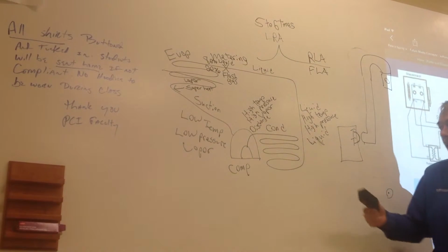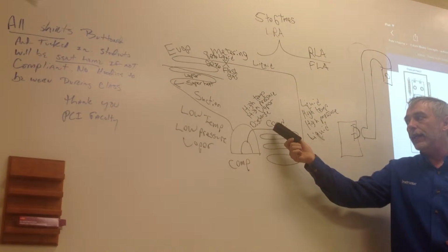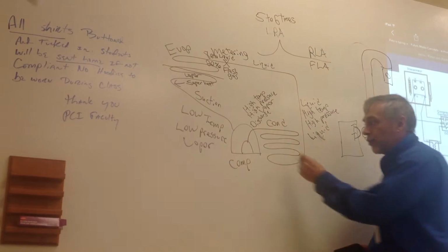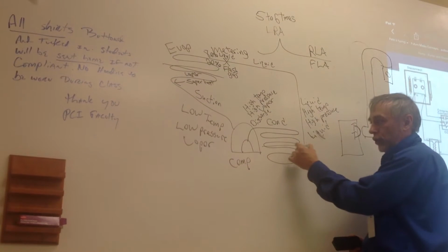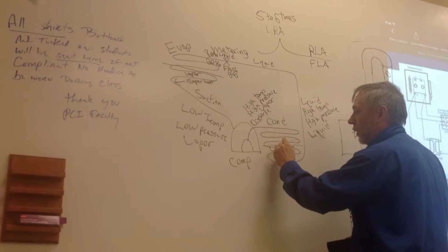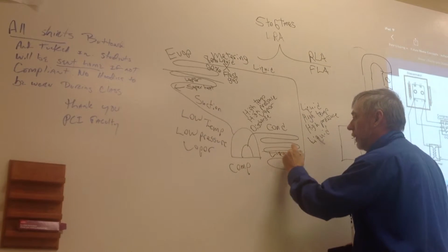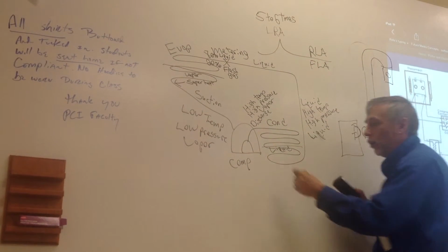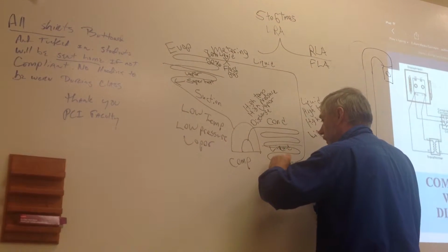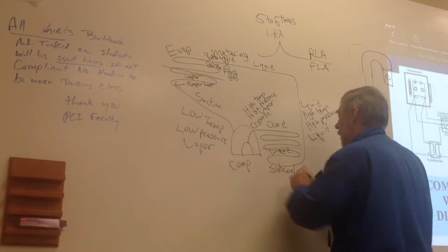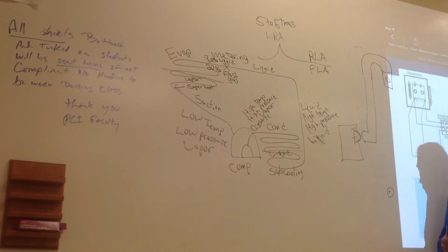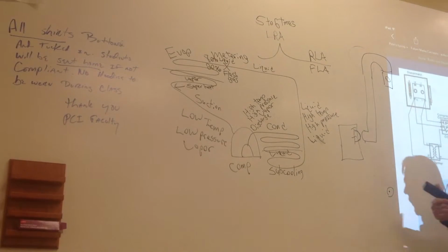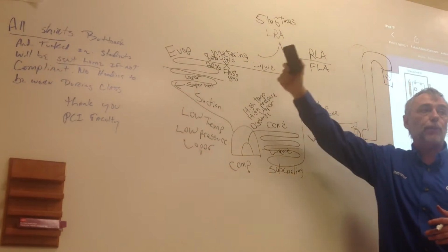And then on the other side over here, where we have taken that high temperature, high pressure vapor and condensed it, approximately 40 to 60% of the way through it should all be liquid. And on this last pass or two, we are subcooling our liquid, taking a little bit more heat out of it, okay? We'll get more into that, but I just wanted to draw up that basic refrigeration cycle.